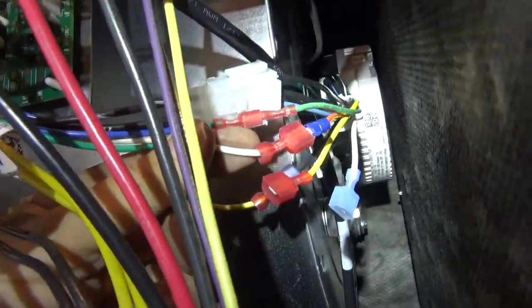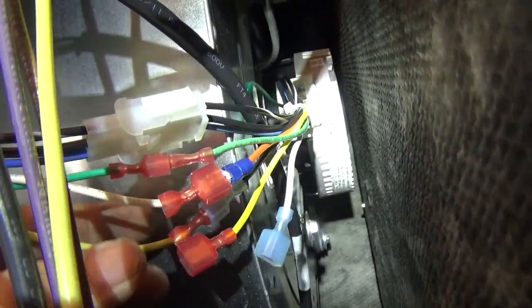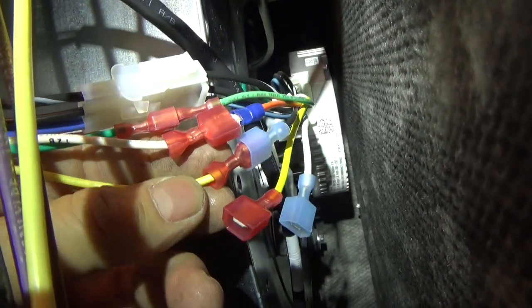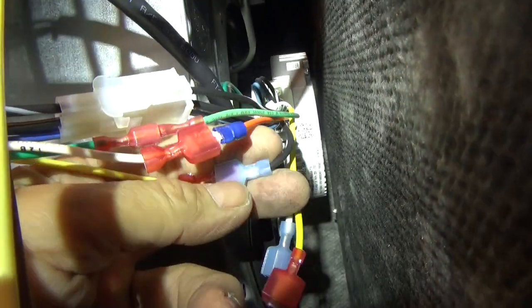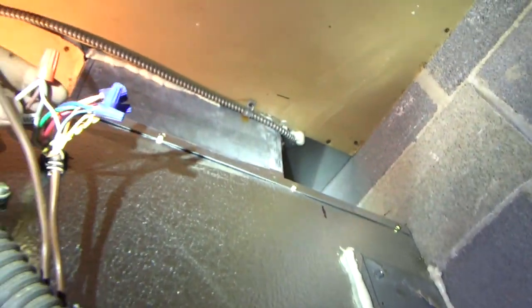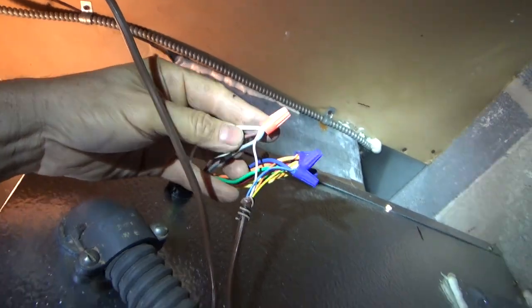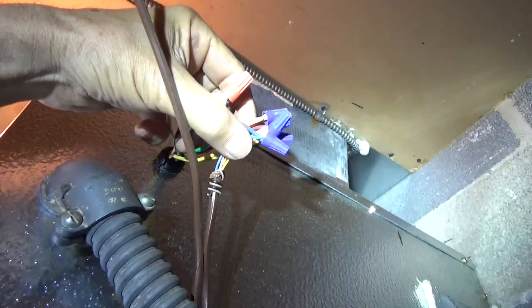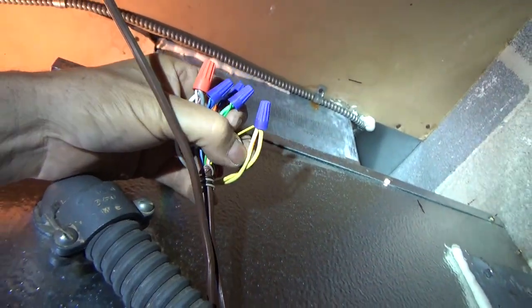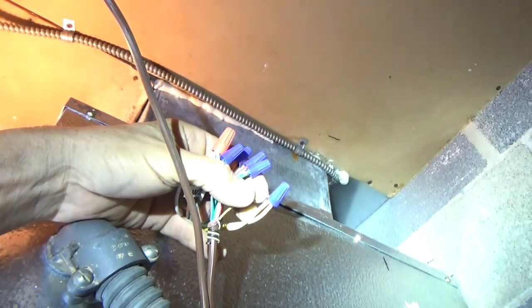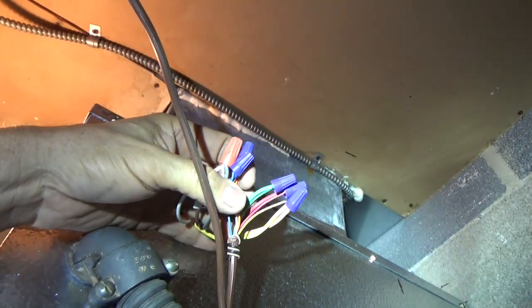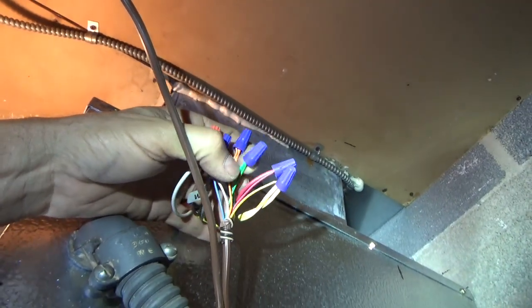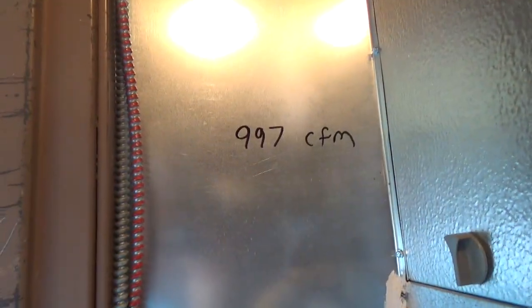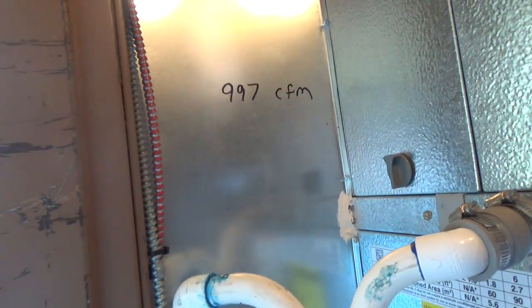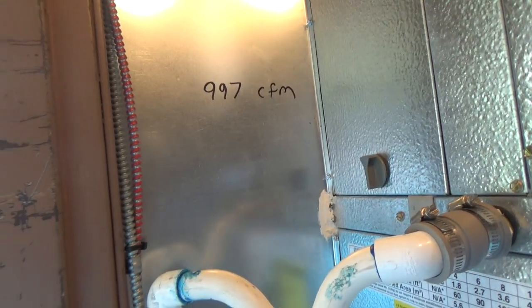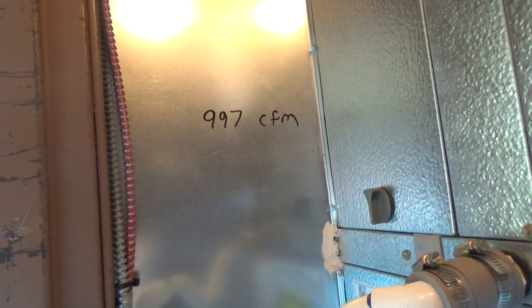Here's a real quick on the wiring. We got our heat on our orange wire, and then we got our cooling/heat pump on black, which is the highest. And then I'll show you real quick here. So all 3 wires for heat. There's a W2. There's also a Y2 which isn't used, but they both go to Y. And then everything else is straightforward, common, reversing valve. And then write your airflow on your return. That way the next guy knows. If this was a 2-ton, it would be 800 CFM. If this was a 1.5 ton, it would be 600 CFM.